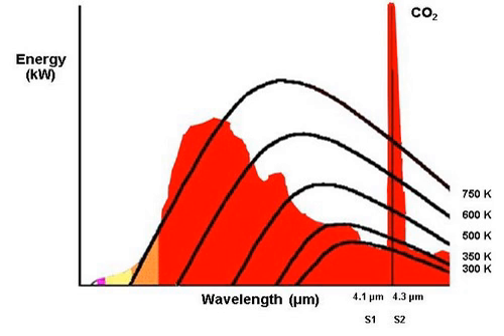Topic: 3IR plus UV flame detection. Multi-infrared, multi-IR, 3IR detectors use algorithms to determine the presence of fire and tell them apart from background noise known as black body radiation, which generally reduces the range and accuracy of the detector. Black body radiation is constantly present in all environments, but is given off especially strongly by objects at high temperature. This makes high-temperature environments, or areas where high-temperature material is handled, especially challenging for IR-only detectors.